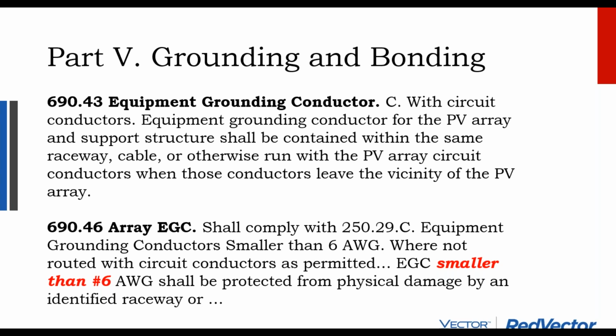So the array needs to be grounded. The metal parts on the roof need to be grounded. If your ground is smaller than number 6, then it needs to be protected. But you're allowed, and what's quite common is to run bare copper number 6 up to the rooftop as the ground and just land on your solar array. That's a simple way to do it.